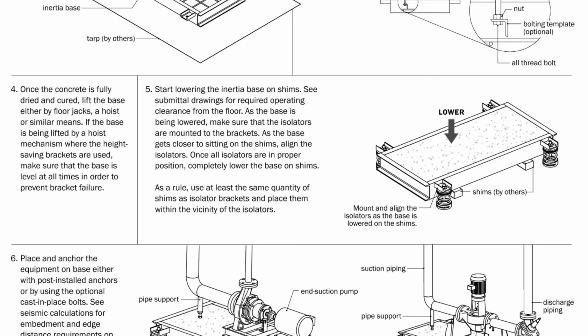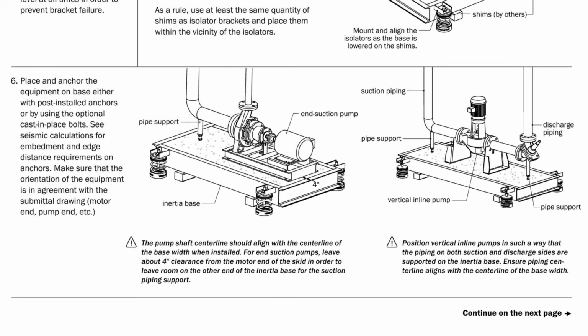Once the concrete has cured, the inertia base will be placed on shims to ensure the correct operating height, but as we'll see soon, those shims are only temporary and should not still be in place once the equipment is operating. This is also the step where the isolators are positioned and aligned. Here we see that the equipment is to be correctly positioned on and secured to the inertia base. The pump should be squared away on the base and its center line should be the same as the inertia base center line. It should be anchored to the base with concrete anchors or pre-installed template bolts.